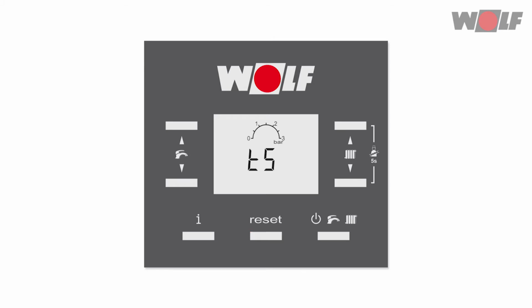Contractor parameters. When the menu TS has been selected via the reset button, the first parameter to be displayed is H01. Press the domestic hot water buttons up and down to select one of the parameters H01 to A09. To view or adjust the value of the selected parameter, briefly press one of the heating buttons up and down. The set value is displayed. Press the heating button up and down to modify the set value. The modification is immediately applied and saved. Press the reset button to exit the parameter level.